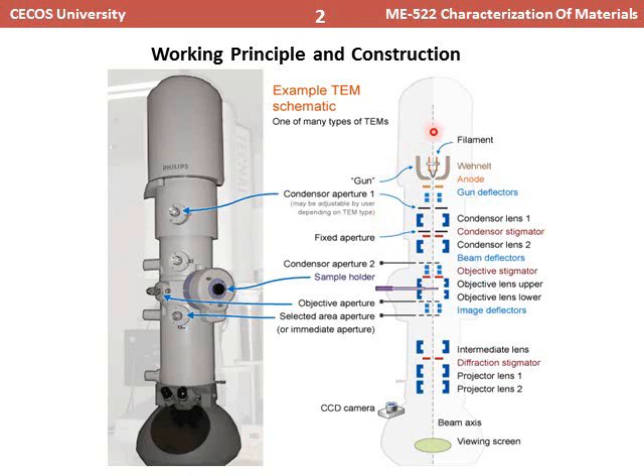Starting from the top, the electron gun is where the electron beam is generated and transmitted. This beam first passes through the electron gun deflector, then through condenser aperture number 1. After that, the beam passes through condenser lens 1 and 2, with a fixed aperture and condenser stigmator located between them.